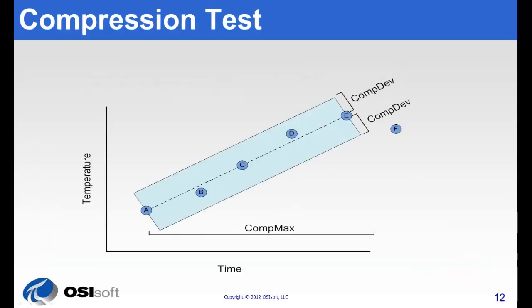The next test is compression. This is a more thorough test and defines which data is stored in the PI archives. Unlike exception, compression can have a slope. This is why we sometimes call it the swinging door algorithm, because it looks like a door viewed from above with a width and a length, and it can swing to match the slope of the data.